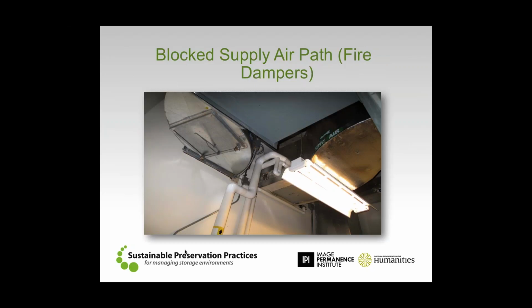Whenever you see a particular portion of a zone, or a zone, going out of spec or out of set point, even though the system appears to be doing the right thing, check your airflow and go back up to the ductwork and start shining flashlights down these access hatches. Make sure that you don't have some sort of obstruction somewhere within that air path that is keeping your supply air condition, whether it's cooling or whether it's heating, from ever reaching that downstream zone.